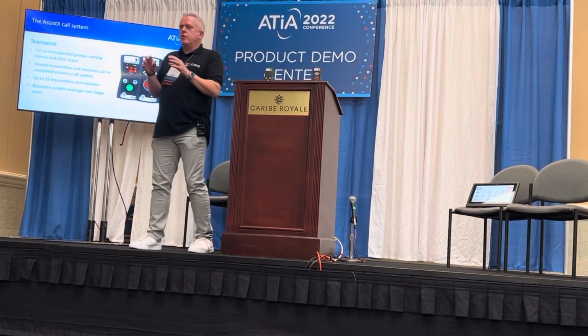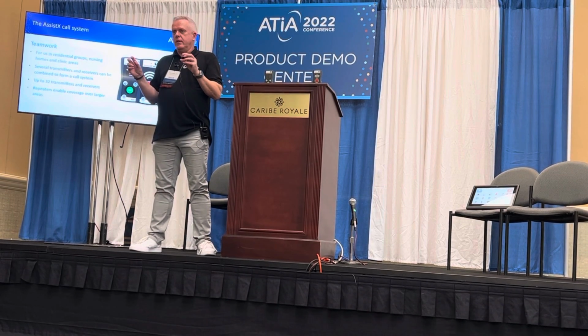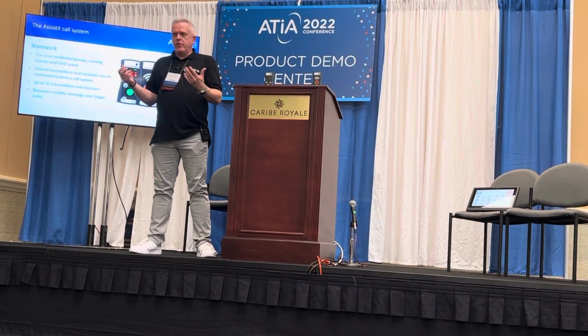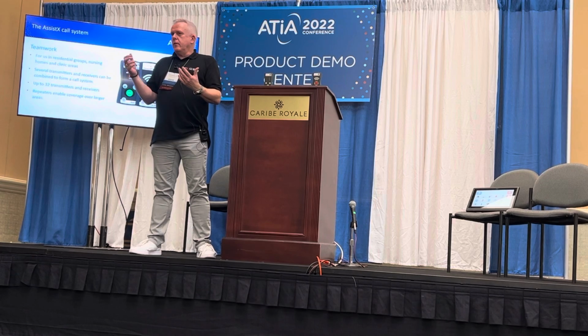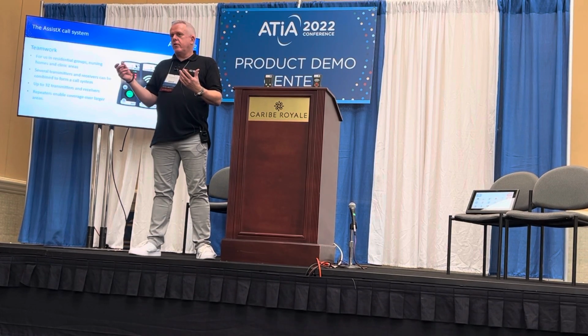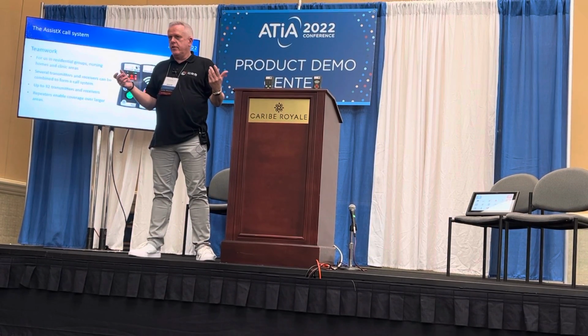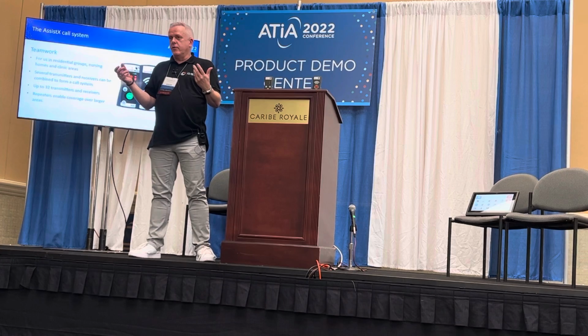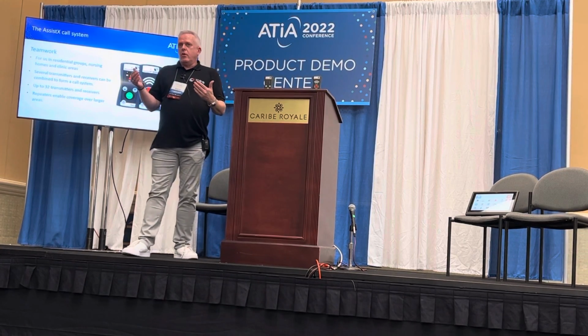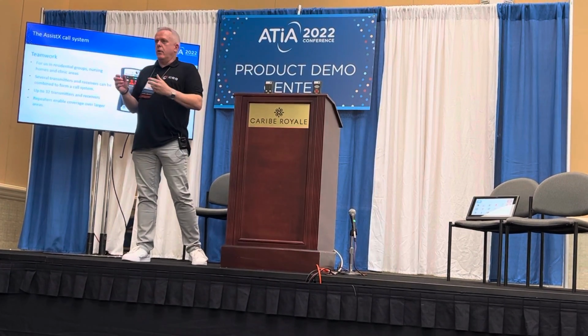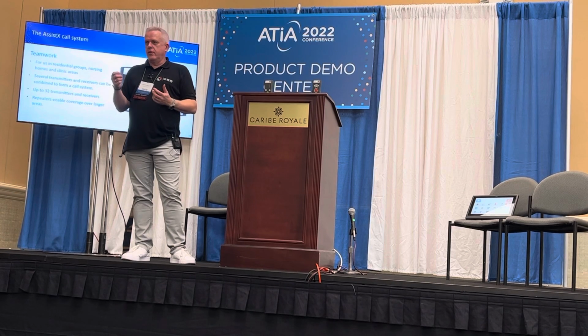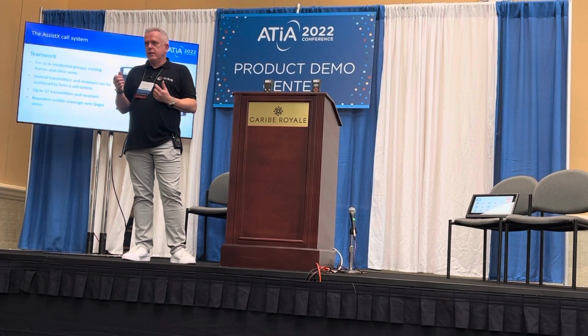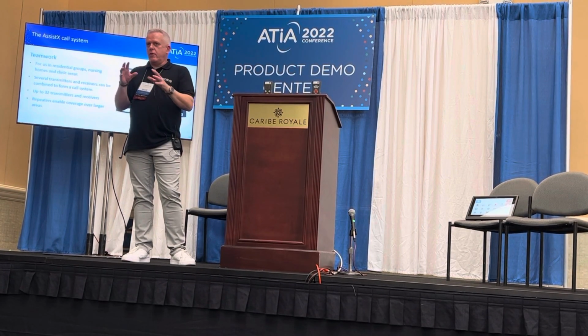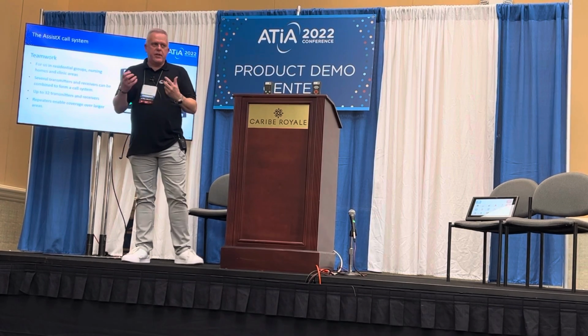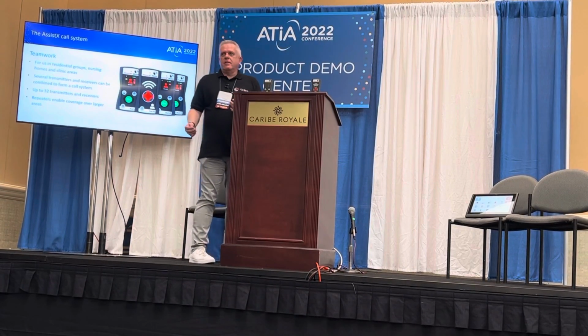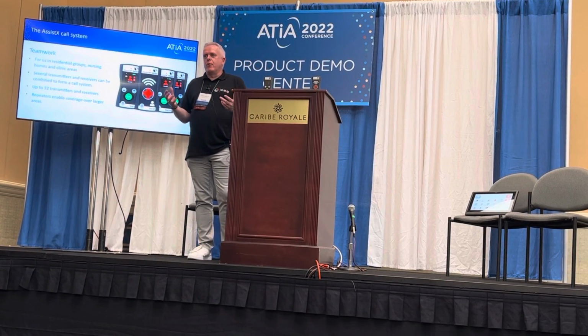If an alarm goes to more than one receiver, you have to confirm it on the receiver, as I did before. If you confirm it on one receiver, that receiver tells all the other receivers, I already received it. The reason is you don't want all the caregivers running to one room - only the one who confirmed the call as the first one. So this system automatically recognizes what's going on, and for everyday use this functionality is very important.